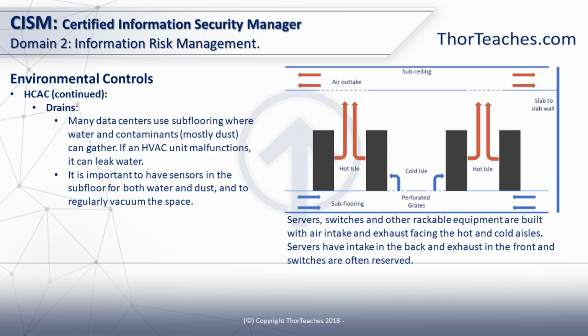When we put servers and networking equipment into our racks, they're all designed to be facing the same way. They have fans pulling air in one end and fans pushing it out the other. The common design for a server is that the air intake is in the front and they push the air out the back, and this is where the hot aisles and the cold aisles come in.